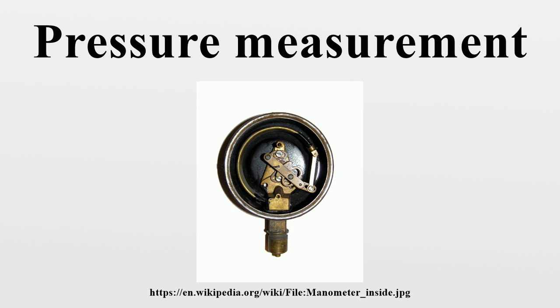Moderate vacuum pressure readings can be ambiguous without the proper context, as they may represent absolute pressure or gauge pressure without a negative sign. Thus, a vacuum of 26 inHg gauge is equivalent to an absolute pressure of 30 inHg minus 26 inHg, which equals 4 inHg.